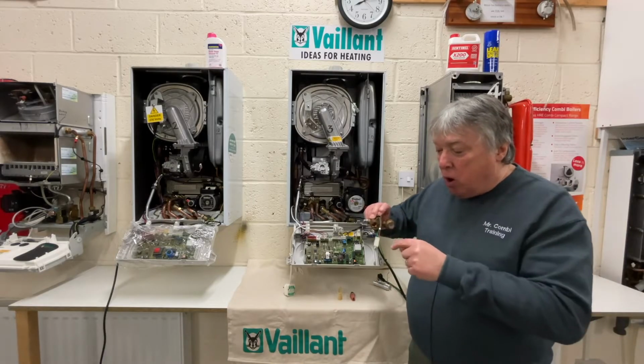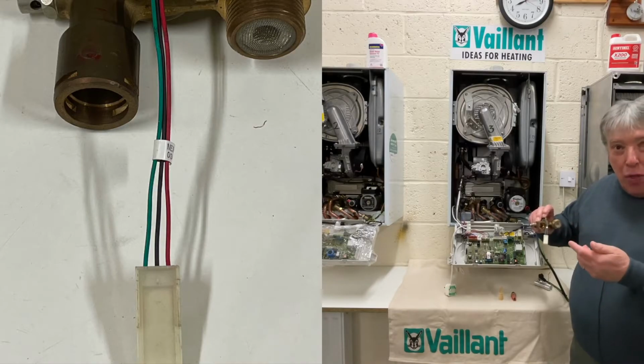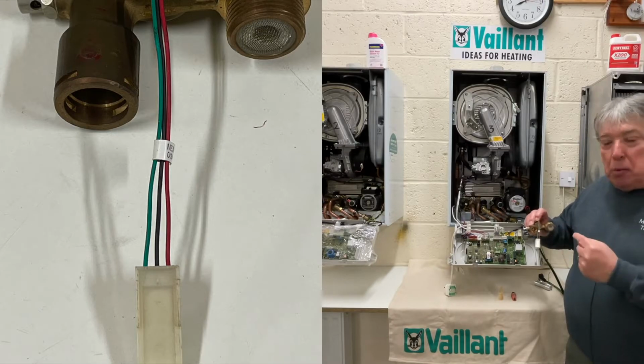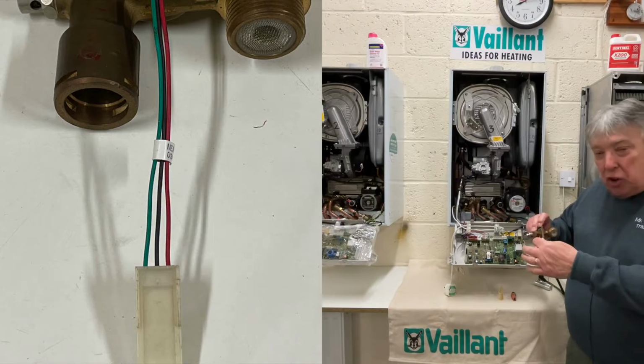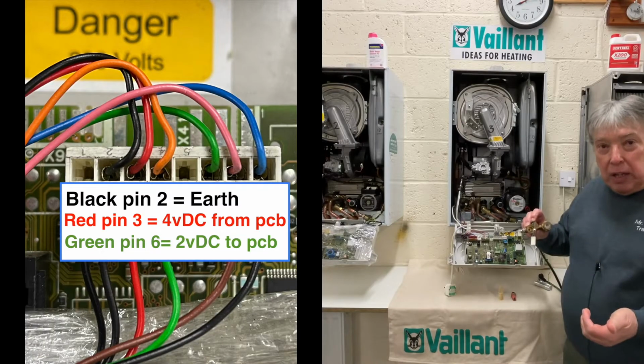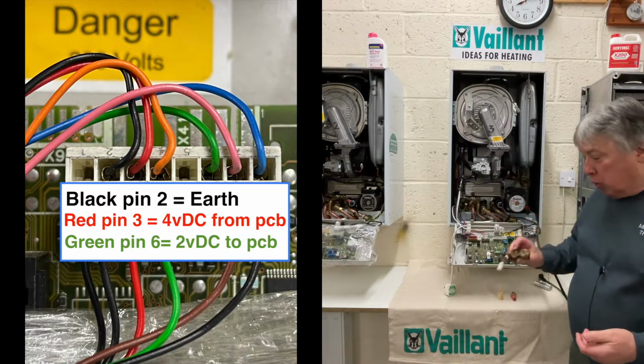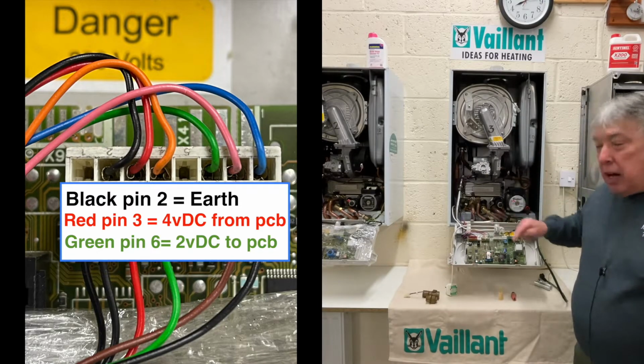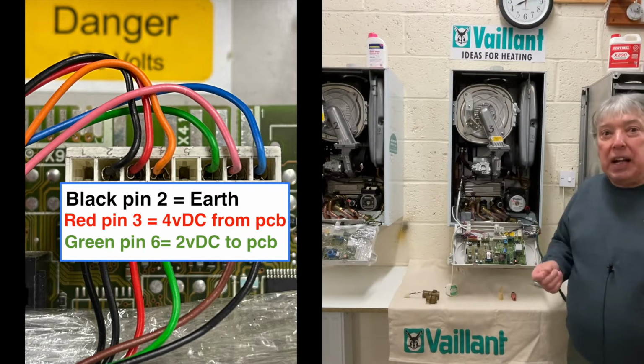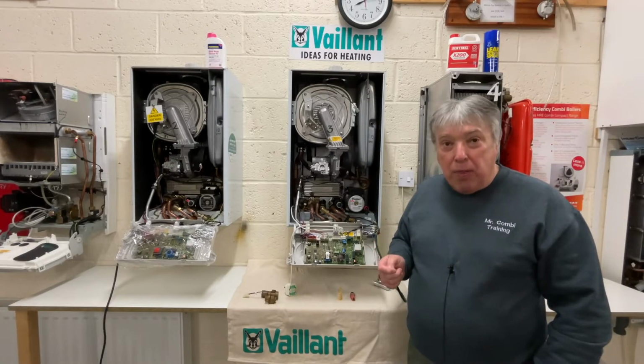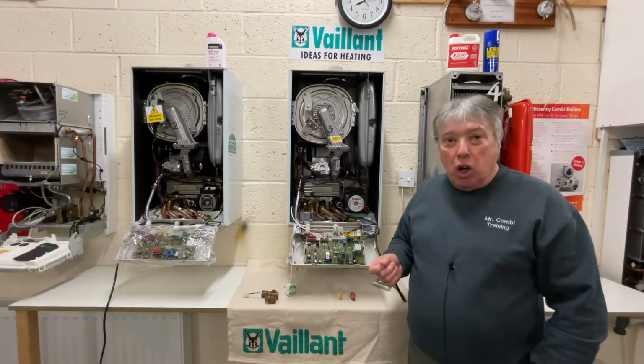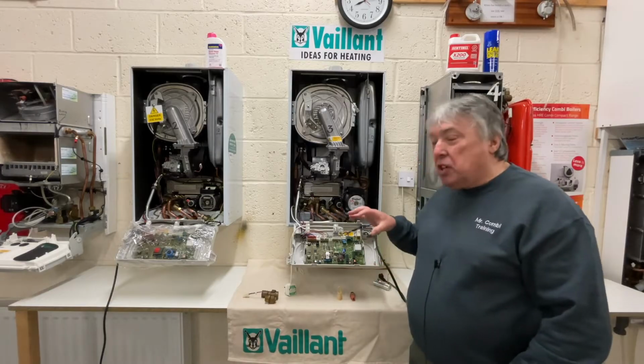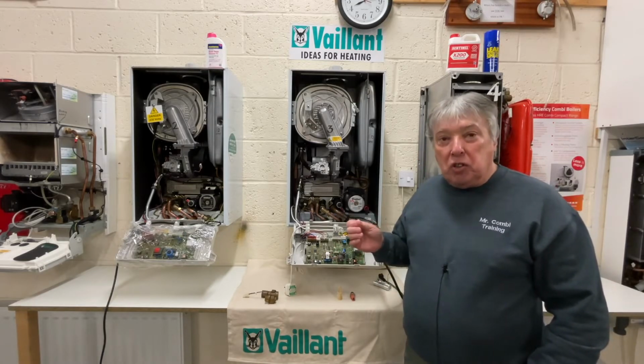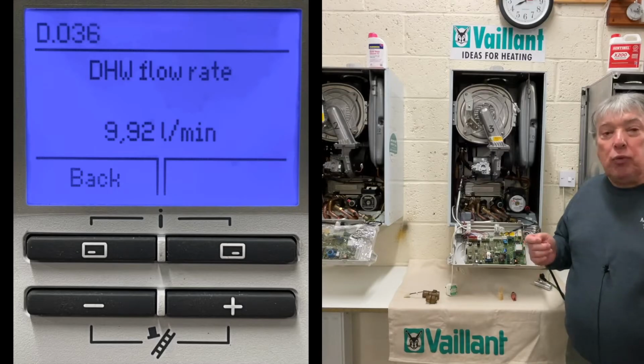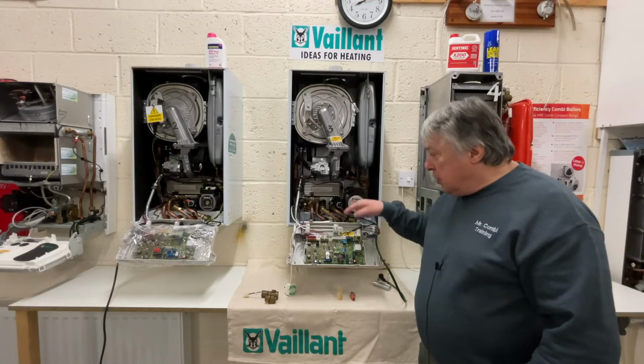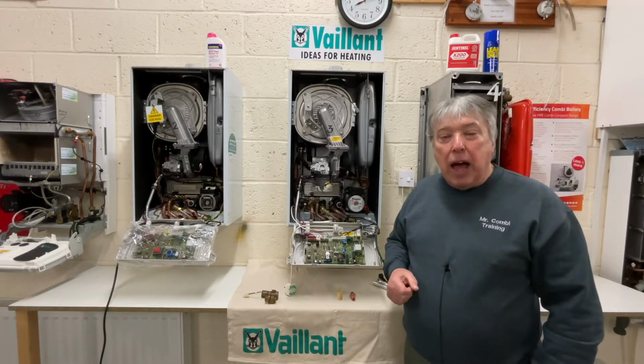And you've got 3 colored wires. Black is earth, red is 4 volts from the PCB into the sensor, and green is 2 volts leaving the aqua sensor once the hot tap is turned on. So it's all located down here, and in the following videos I'll show you exactly how to test in various methods, whether we use volts DC, hertz, and the displays. So it's in the diagnostics level, which is D36 for the actual flow rates in litres per minute. So this is the beginning of the Vaillant Aqua Sensor.